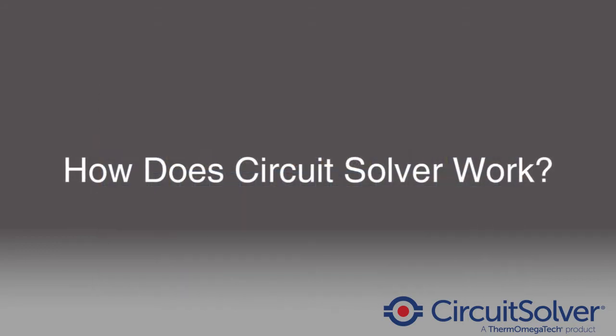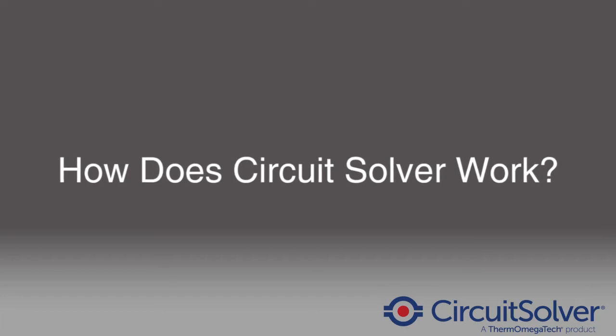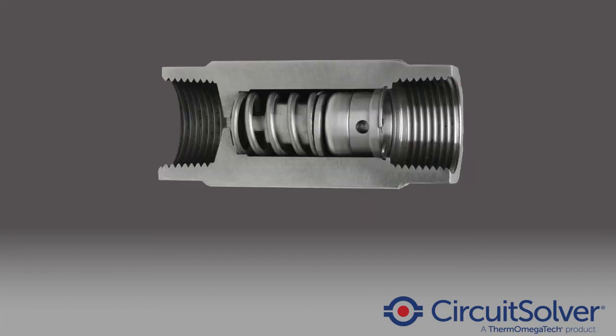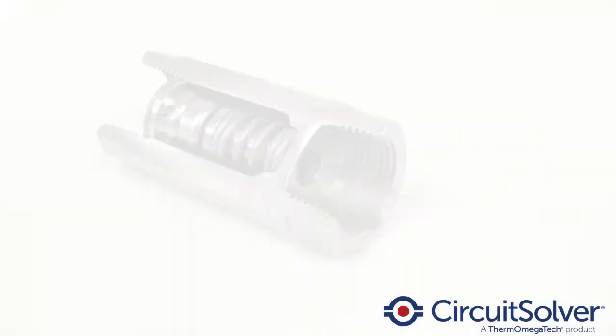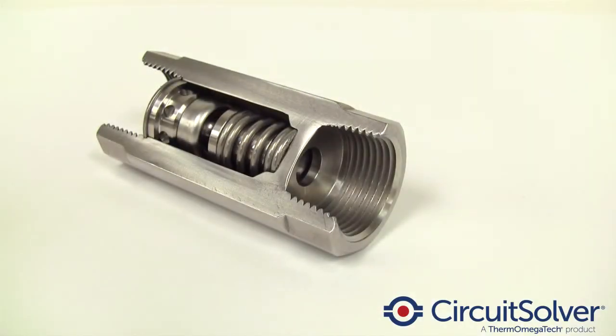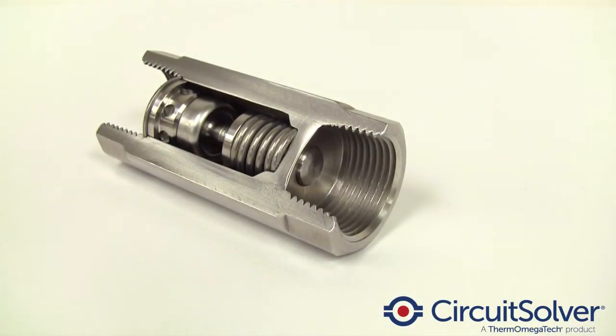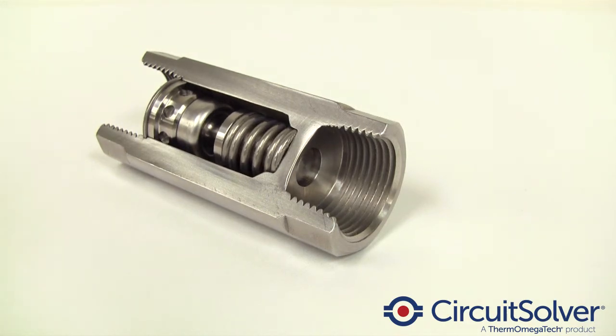You are probably wondering how CircuitSolver accomplishes this amazing feat. CircuitSolver is a thermostatically activated flow control valve. As water enters the valve, the thermostat senses the temperature and increases or decreases flow based on the set point of the thermostat.